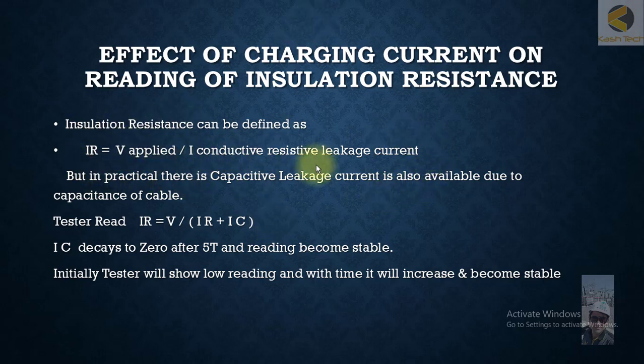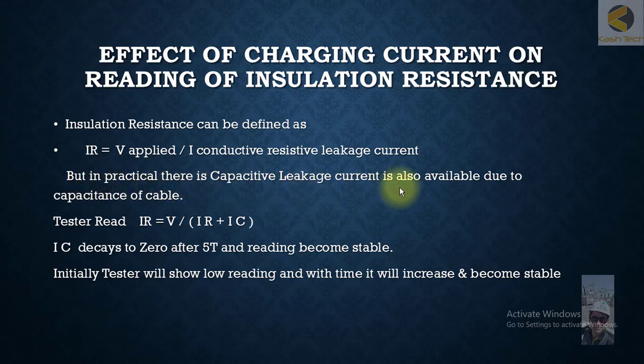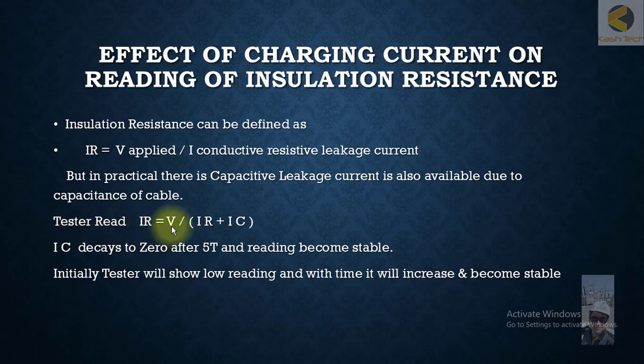Additionally, there is a charging current which will effectively reduce the insulation resistance value. In practice, a capacitive leakage current is also present due to the capacitance of the cable. So the tester will read insulation resistance as equal to V divided by IR, which is the resistive conductive current, plus IC, the charging current.